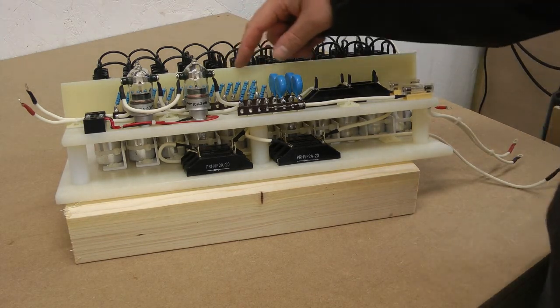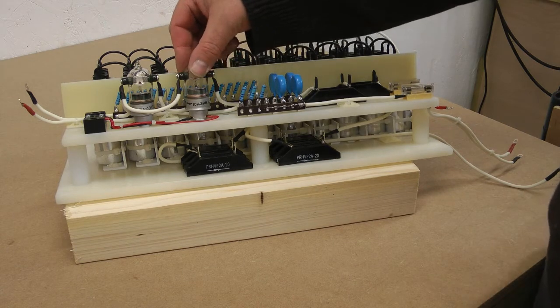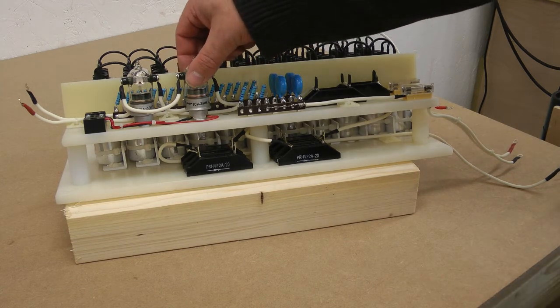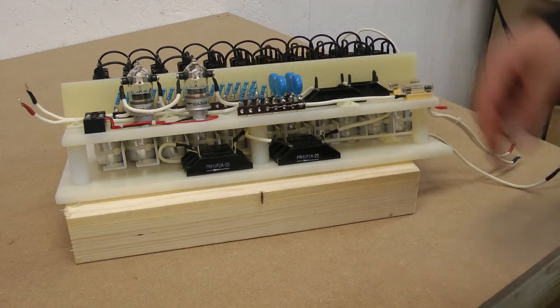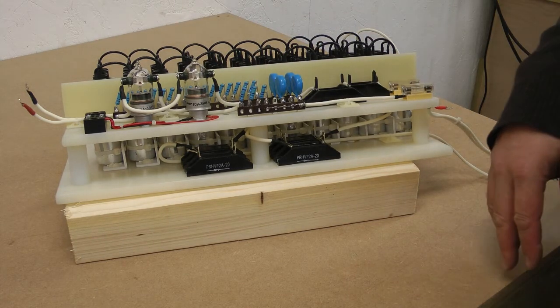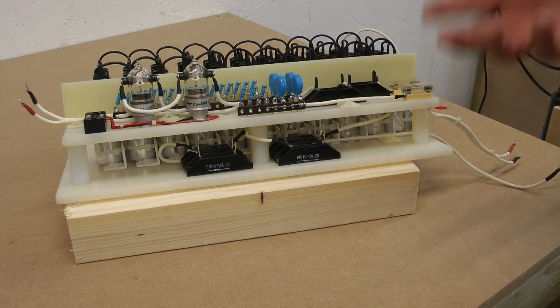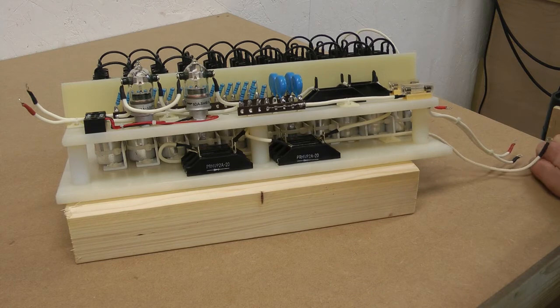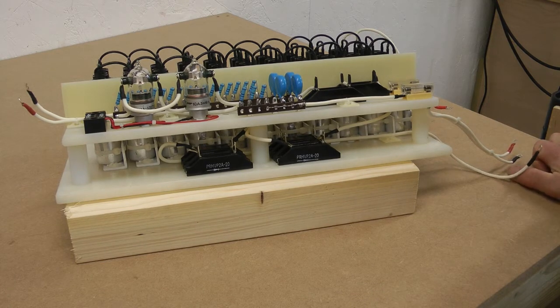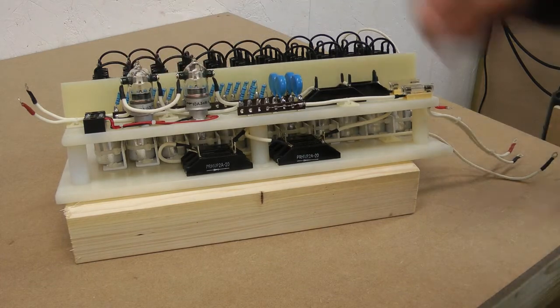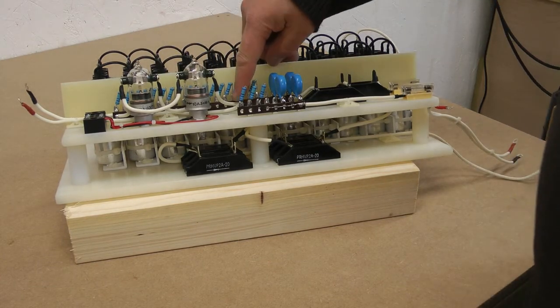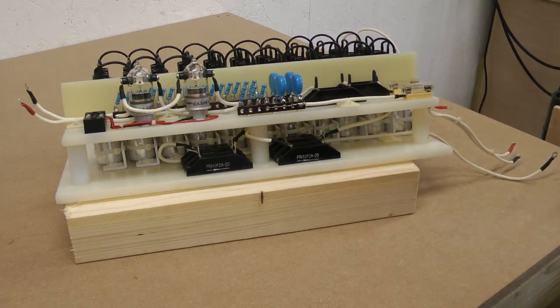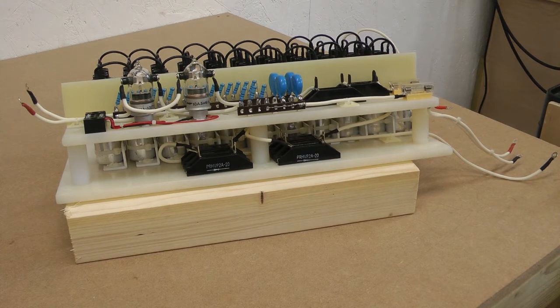Now, you might say, well, how can you put 20 kilovolts, or somewhere up about 15, onto a 3 kilovolt relay? Remember that we have considerable resistance here. So the terminals can't arc over because the current is very, very restricted. That's why you can use these kind of relays in this kind of situation to basically bridge from a different point in the divider to the output. And that works very effectively in being able to safely switch the high voltage in different ranges on the front panel.